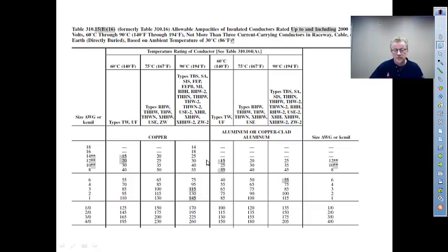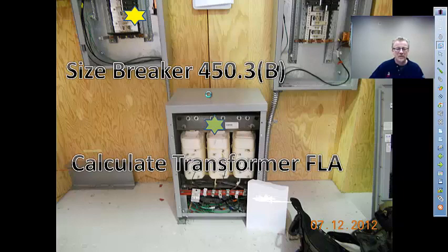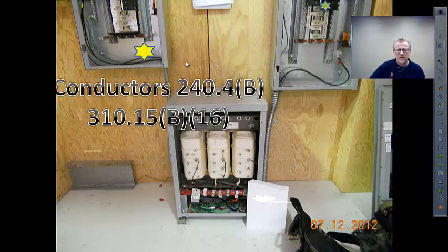A 70 amp breaker can protect a number 6, 75 degrees C on the copper side. Follow that out, and we're talking about a 65 amp wire is allowed to be protected by a 70 amp breaker as long as we apply 240.4(B). 240.4(B) says if we have an ampacity that does not correspond to a standard rating, we can protect these conductors at the next higher standard rating or setting. So we have 65 amp wire. It's certainly large enough for that 54 amp load. And then we are going to protect it at 70 amps. A 70 amp breaker is the largest that it could be.